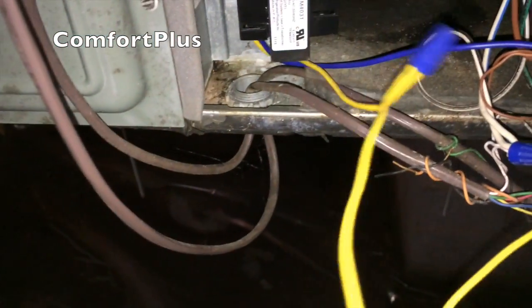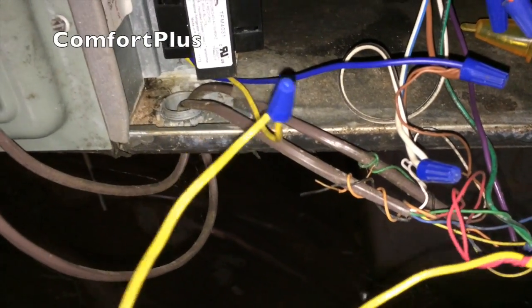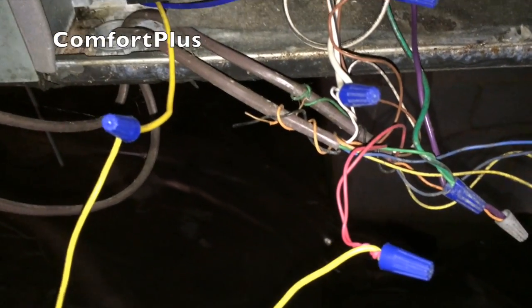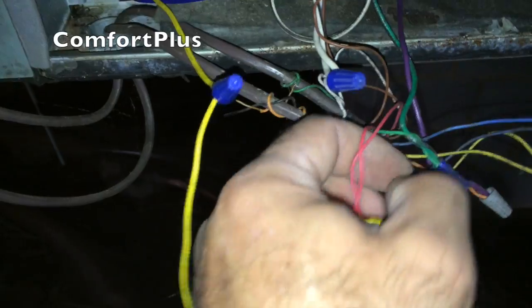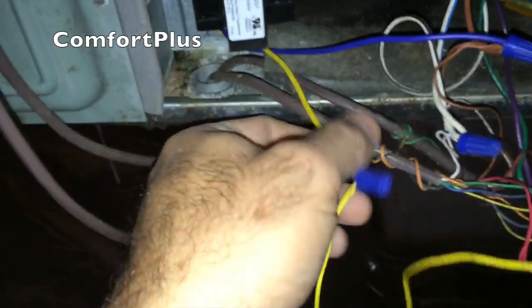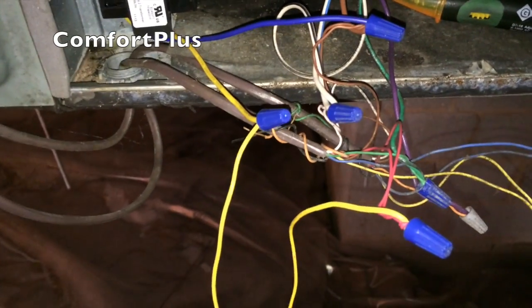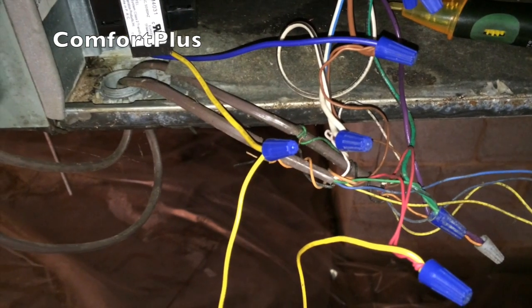Because I don't know what happened to this transformer yet, I haven't turned anything on. I've stuck a little 5 amp circuit breaker in the line. I'll check amps on everything once I start it up here and make sure it was just a faulty transformer and not a bad contactor or sequencer or something, or even a short that caused the transformer to fail.